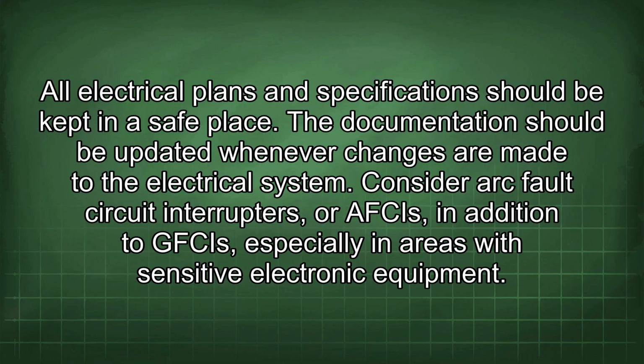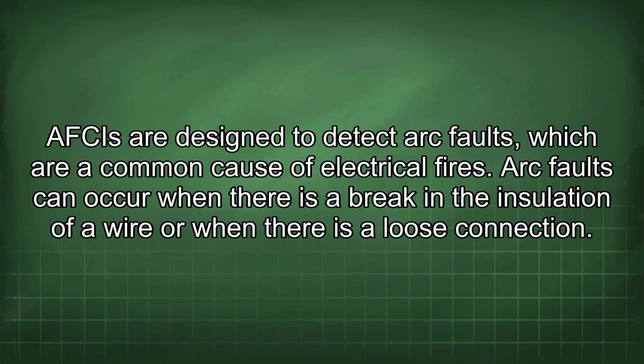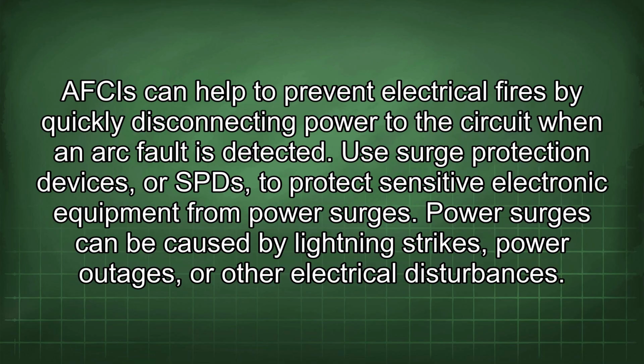Consider arc fault circuit interrupters, or AFCIs, in addition to GFCIs, especially in areas with sensitive electronic equipment. AFCIs are designed to detect arc faults, which are a common cause of electrical fires. Arc faults can occur when there is a break in the insulation of a wire or when there is a loose connection. AFCIs can help to prevent electrical fires by quickly disconnecting power to a circuit when an arc fault is detected.